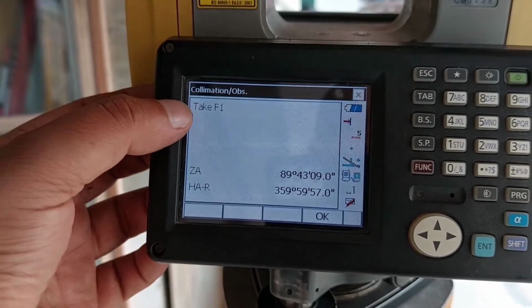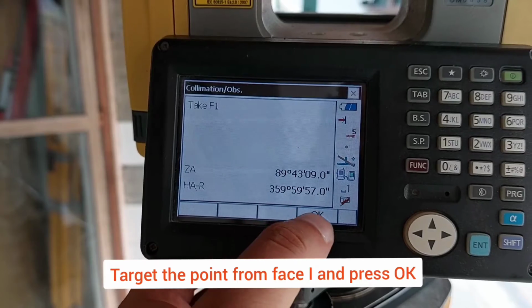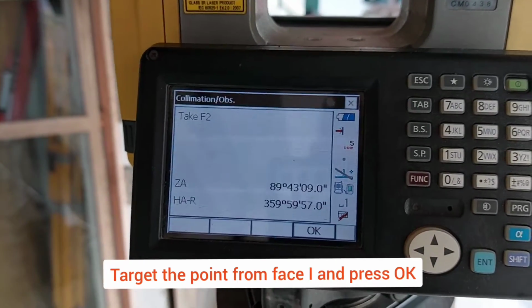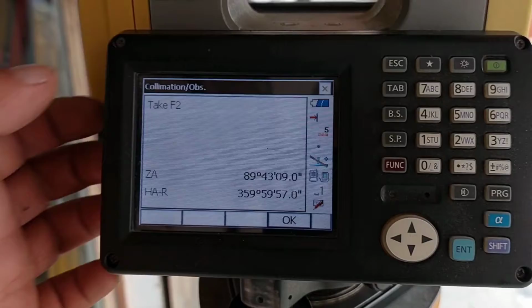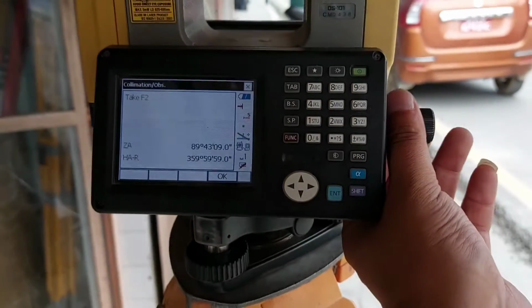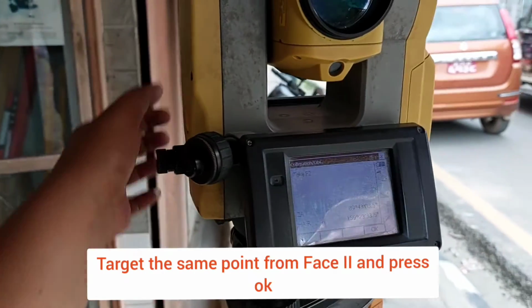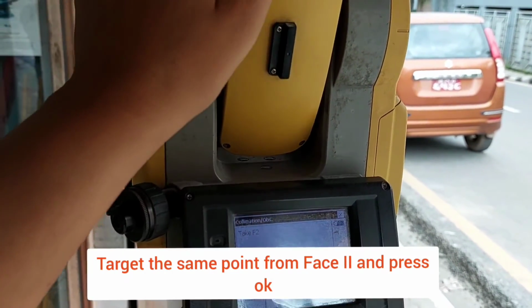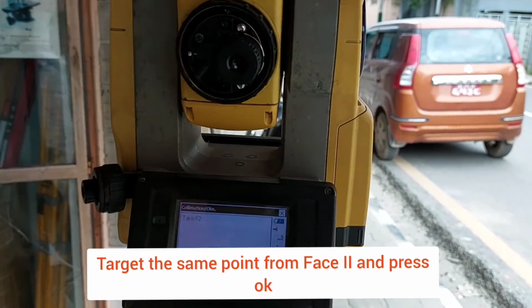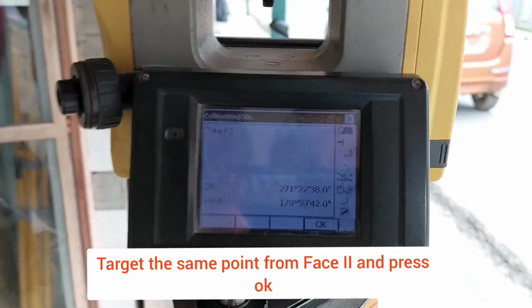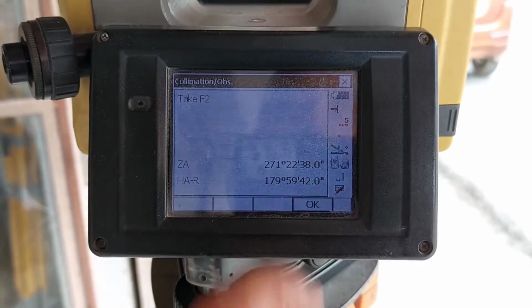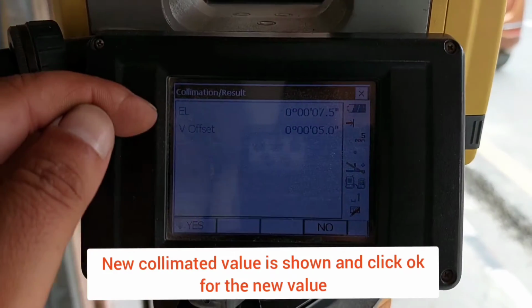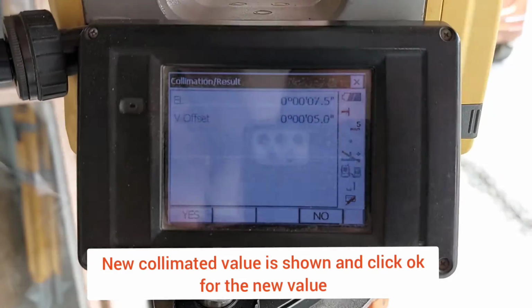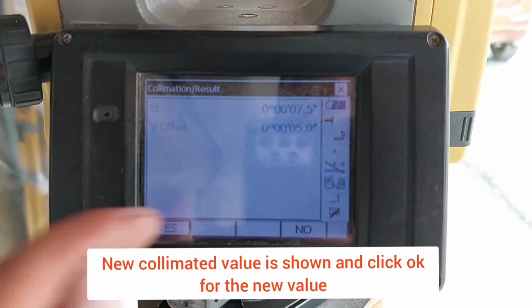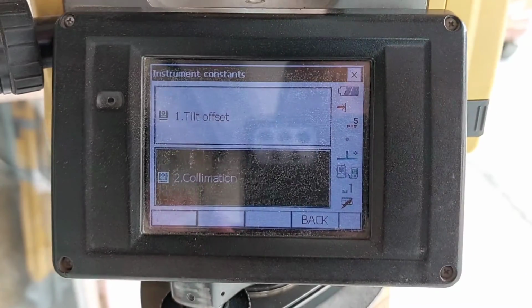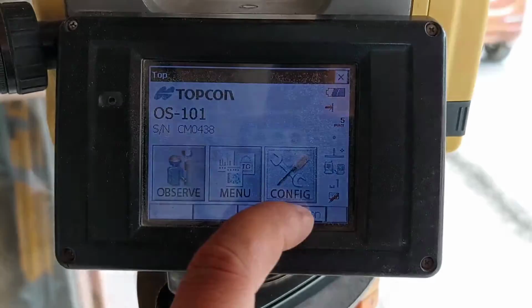Okay, now again take F1, so I'll target it to my crosshair and I'll press OK. Now the device will ask me to take F2. Okay, now I will turn my device to face 2 and target the exact same point. Be careful while targeting, it should be exactly the same point. Now with F2 I am pressing OK. Now you can see my error level is shown. Now if I need to save, I'll press Yes. Now this is done. My new settings are saved.